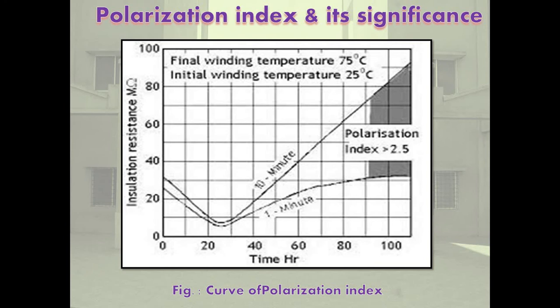For large transformers and for EHV transformers, the IR10 minute reading and the IR 1 minute reading are considered. So PI, the polarization index, equals IR600 by IR60 for a large power transformer. So the first reading is at 1 minute, the second at 10 minute. The polarization index is greater than or equal to 2.5. The final winding temperature is 75 degrees Celsius. Initial winding temperature is 25 degrees Celsius. Then the value increases with time.